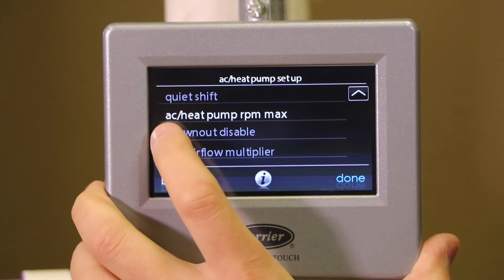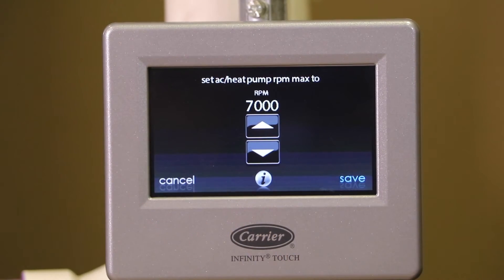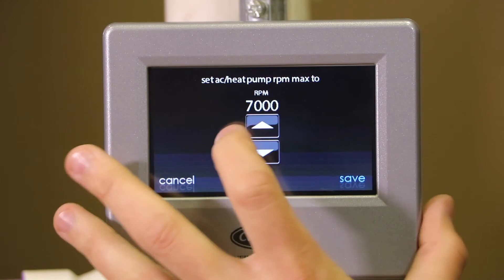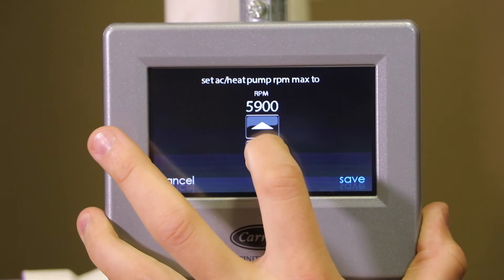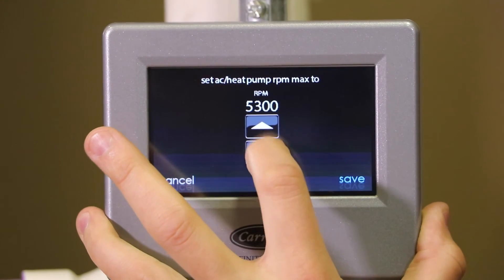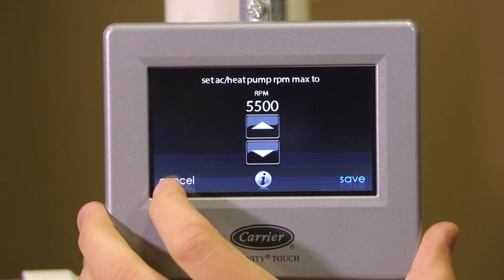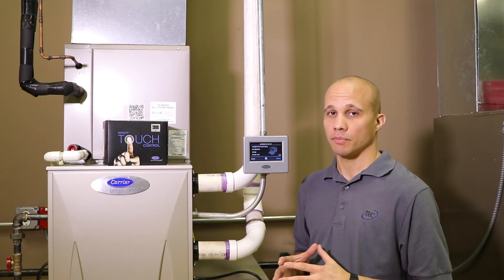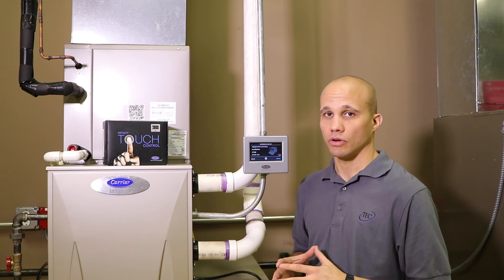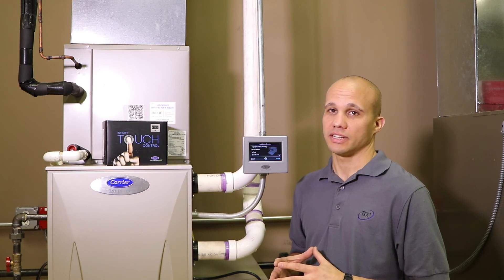The last one we're going to look at is AC heat pump RPM max. 7000 is the default on this particular unit. I can lower that if I want to. This is a pretty quiet unit, but if for some reason a neighbor didn't like it, I could lower the RPM which would lower the sound. It would also lower the capacity a little bit, but it might not be the end of the world. That wraps up our discussion on setting up AC and heat pump settings of the Infinity and Evolution control. Please watch our other videos and remember to like and subscribe, and we'll see you guys next week.